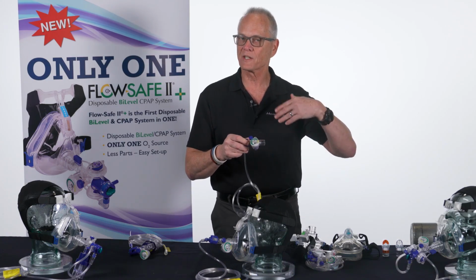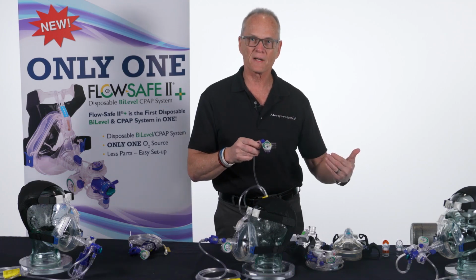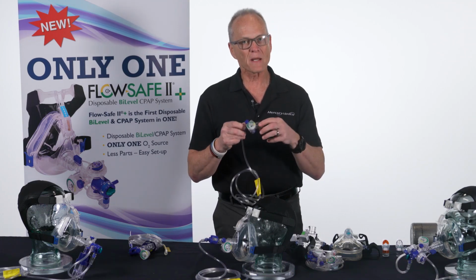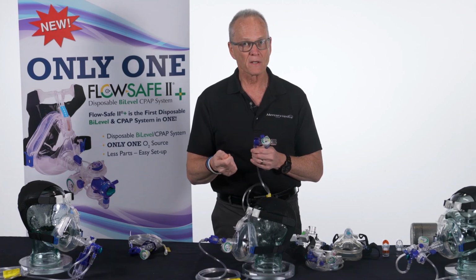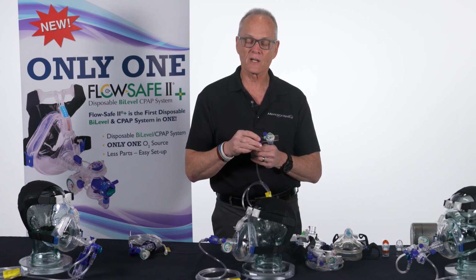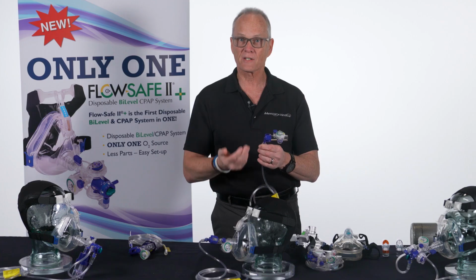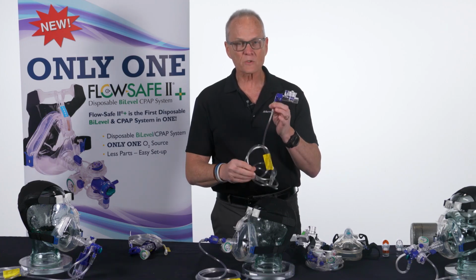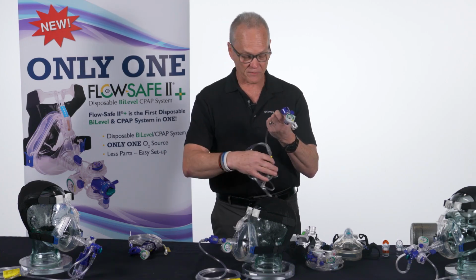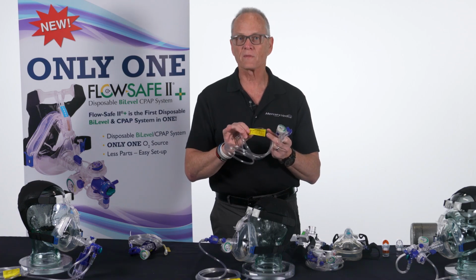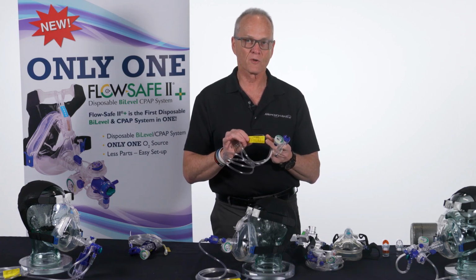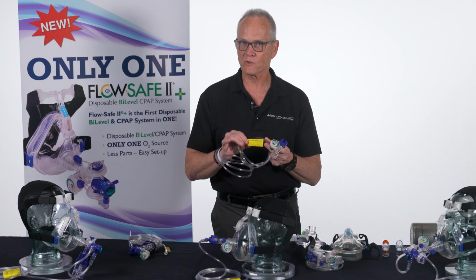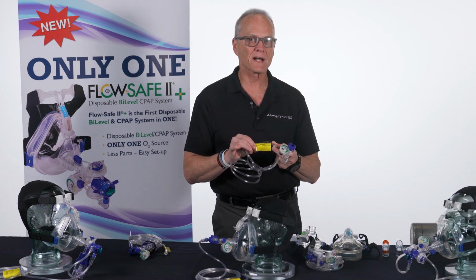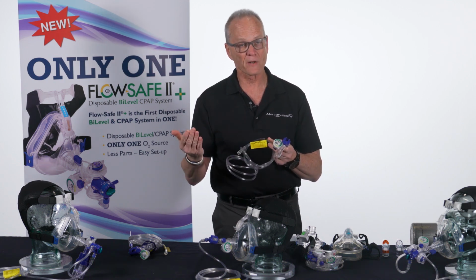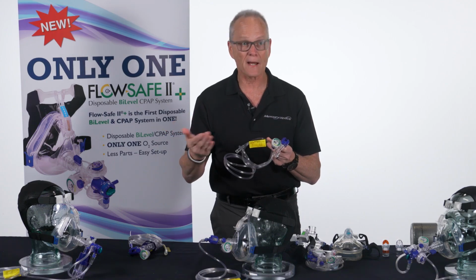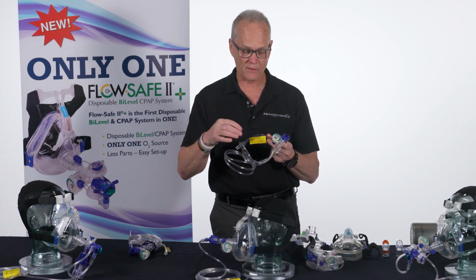And I've seen people want to sedate a patient because they're fighting the device. It's not the patient. It may be the device is not set up correctly, or the device that you may be using doesn't provide the gas flow fast enough. Now, on the FlowSafe 2, on all of our FlowSafe devices, there's a sticker on the end of the tubing that tells you what gas flow will give you what pressure. Now, I tell people to use that as a guideline because sometimes regulators are not calibrated the way they should. They're not adjusted the way they should be.